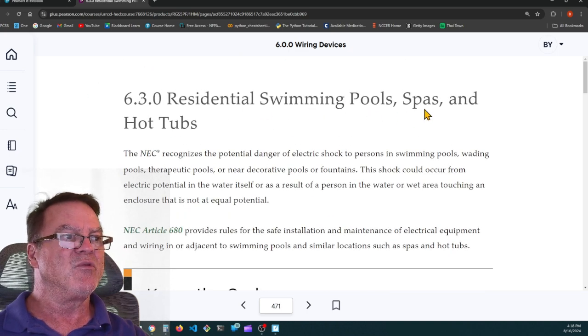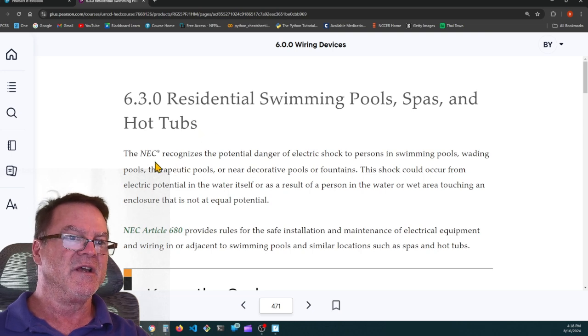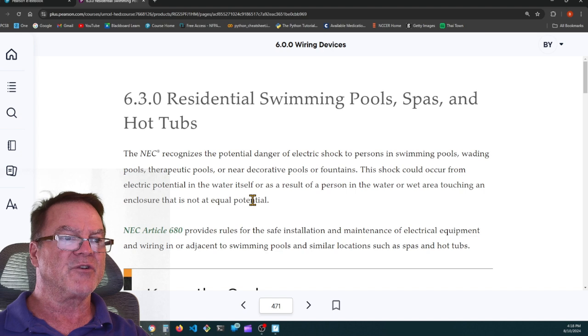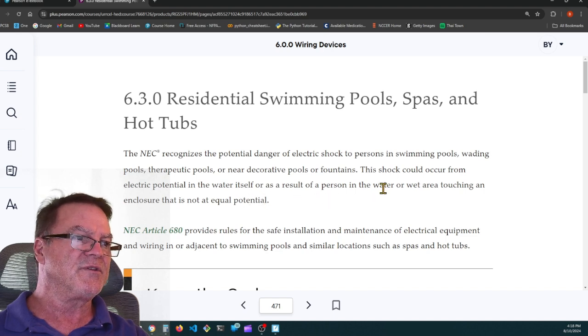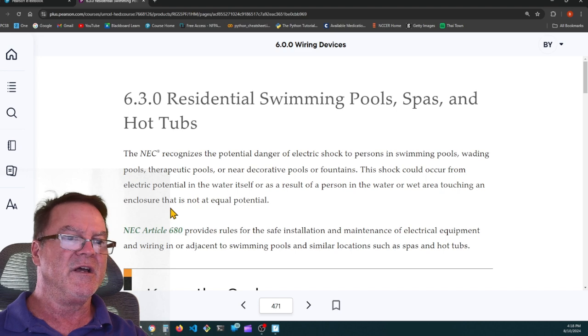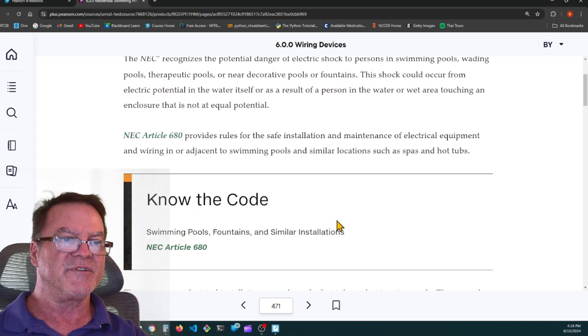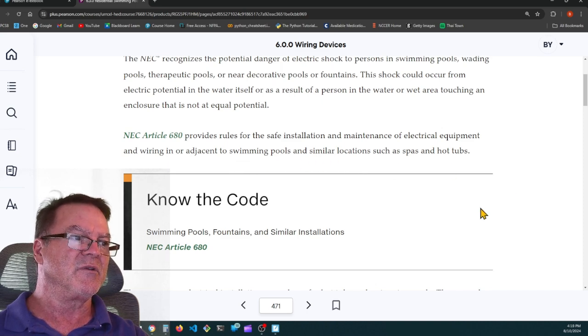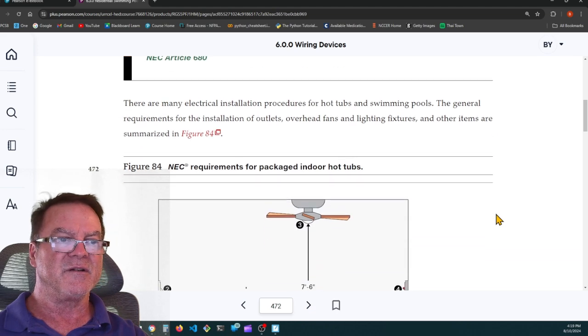Residential swimming pools, spas, and hot tubs. The NEC recognizes the potential danger of electrical shock to persons in swimming pools, wading pools, therapeutic pools, or near decorative pools or fountains. This shock could occur from electric potential in the water itself or as a result of a person in the water or wet area touching an enclosure that is not at equal potential. NEC Article 680 provides rules for the safe installation and maintenance of electrical equipment and wiring in or adjacent to swimming pools and similar locations such as spas or hot tubs.